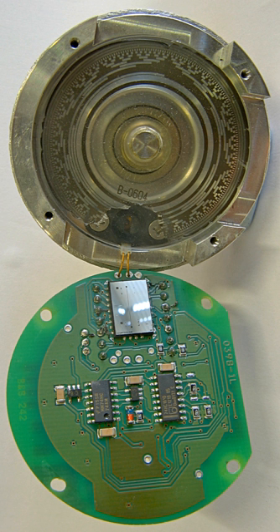Topic: Other pulse output rotary encoders. Rotary encoders with a single output, i.e. tachometers, cannot be used to sense direction of motion but are suitable for measuring speed and for measuring position when the direction of travel is constant. In certain applications they may be used to measure distance of motion, e.g. feet of movement.